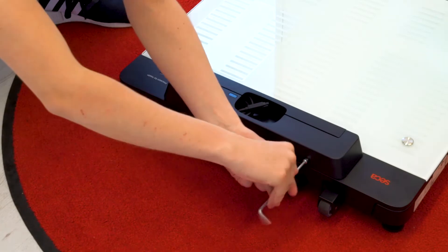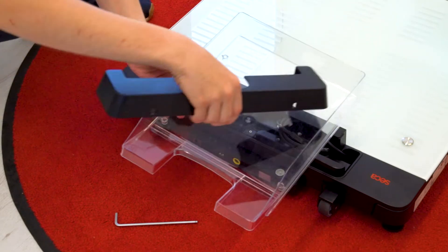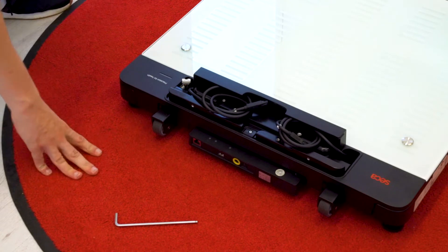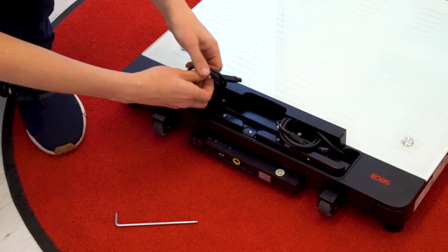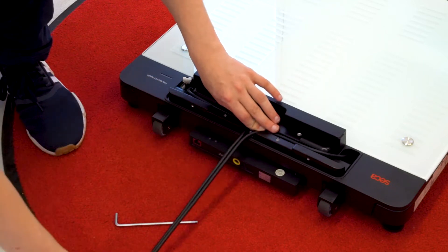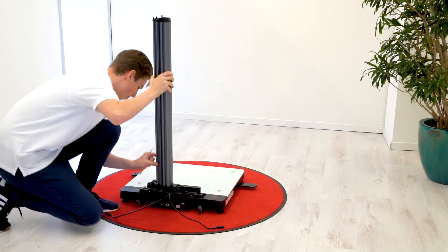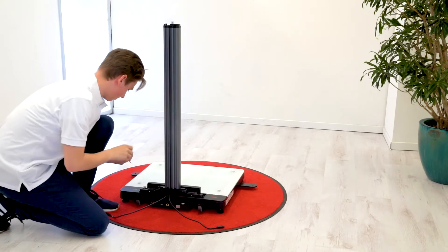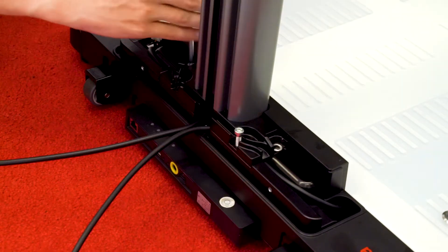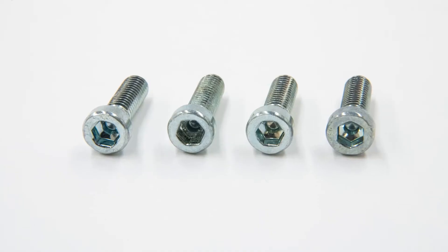Remove the column socket cover with the 4 mm Allen wrench and put aside the cover and associated screws for later reassembly. Beneath the cover, identify the two BIA foot electrode cables and place both cables through the cutout. Next, get the bottom column segment. Slide the segment onto the platform and ensure the proper placement of the cables. Mount the segment on the platform using a 5 mm Allen wrench and four M6x20 screws.